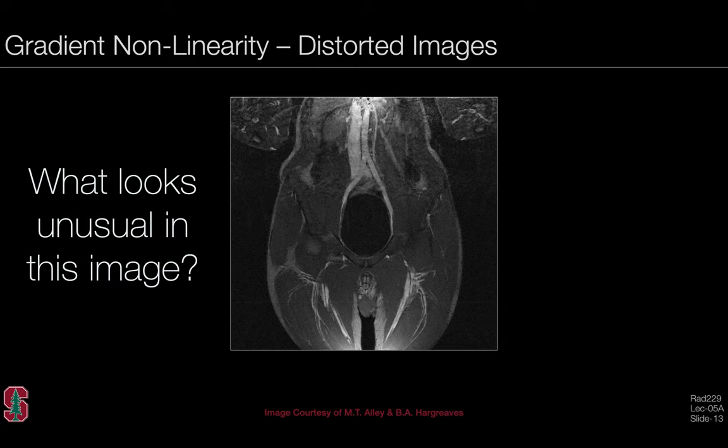So what does gradient nonlinearity do to images? What looks unusual in this image? Go ahead and pause the video for a second and see if you can identify features that seem unusual. The things that stand out are the geometry—it looks maybe pinched at the top and bottom, or more wide in this midsection. You'll also notice a gradient in signal intensity with bunching up of signal, things look brighter in these regions and taper off toward the edges.